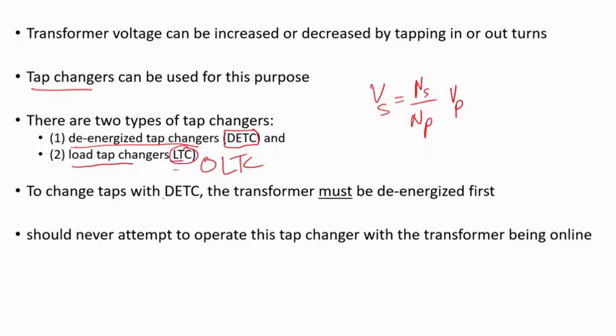To change taps with the de-energized tap changer, the transformer must be de-energized first, and that has to be done manually — there's a handle you have to turn to make the change. You might have a 5% voltage change range, in steps of 2.5%, meaning each tap change is worth 2.5% of the rated voltage. You can have two taps above and two below nominal.